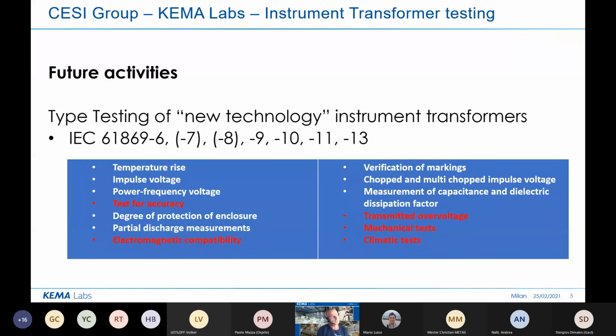But when we now look at the new low power instrument transformers, for instance, then of course there is an electronic part, so we also need to consider the electromagnetic compatibility of the complete solution. And that also means that looking at accuracy, we have to take a completely different approach. Where accuracy in the past was measured purely based on analog values, we now have to do it on digital values. And there then also a timing aspect comes into the picture.